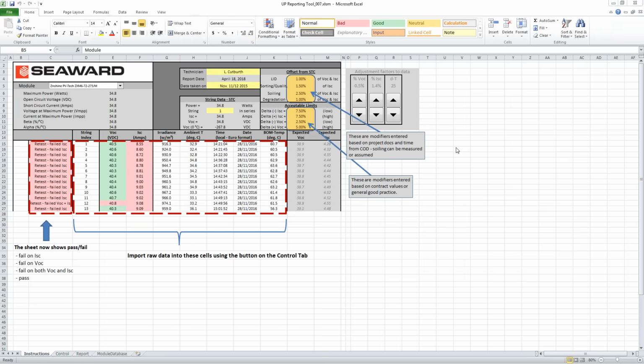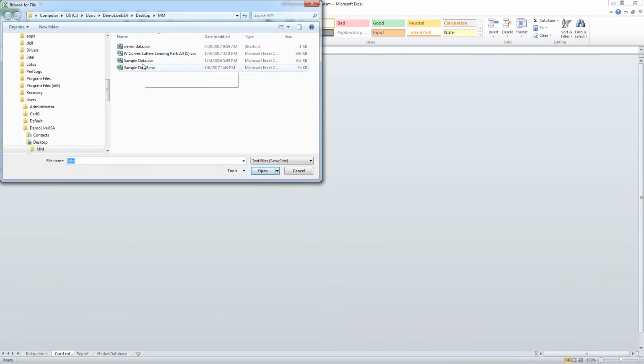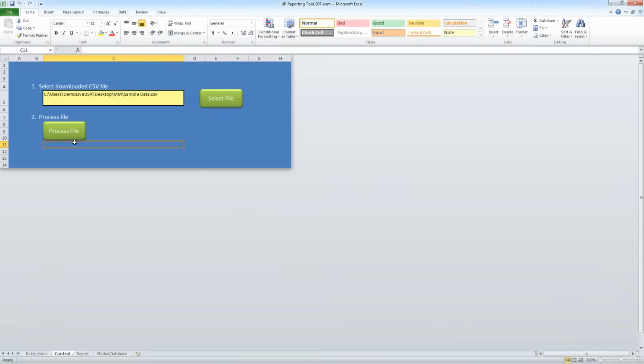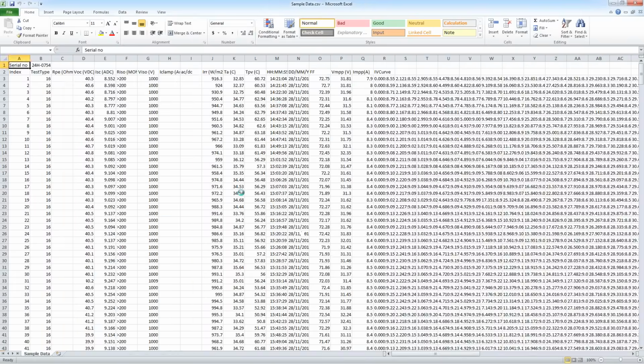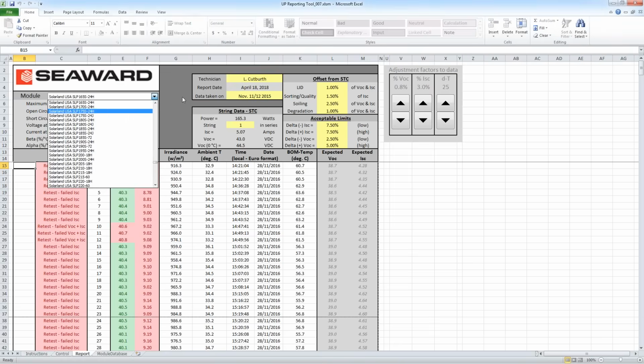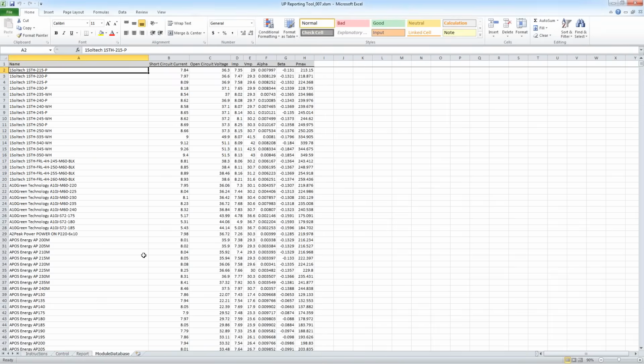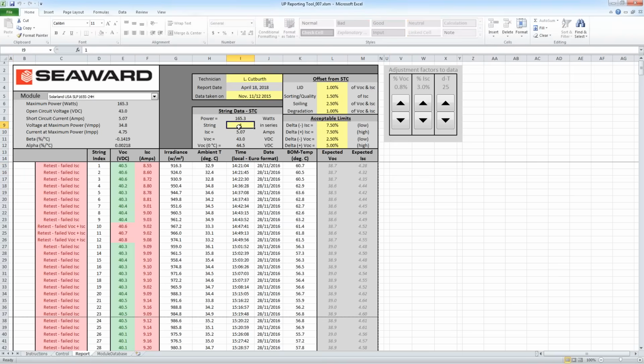Just circling back to the Solar Utility Report for a moment. This is the tool here. So I can import my sample data set here. I will process the file. I could then select a panel, and we have a database of over 18,000 panels, and you can add in your own. We then select the number of panels in the string. We can also set our offsets, and what it will then do is tell us, okay, well, this string was in line with the VOC, but the short circuit current was not in line. And then we have some similar adjustment factors and acceptable limits.